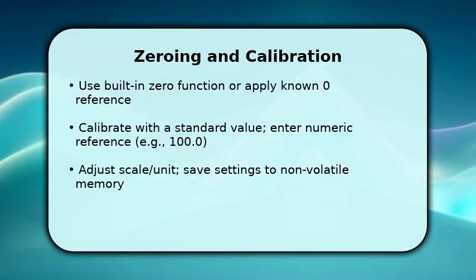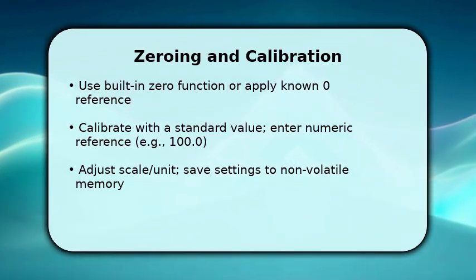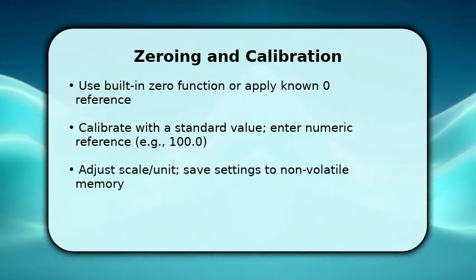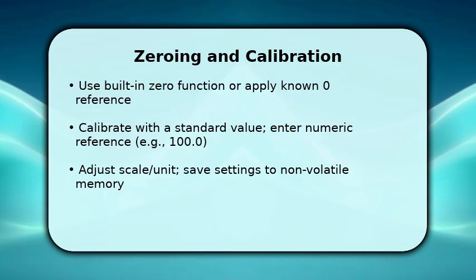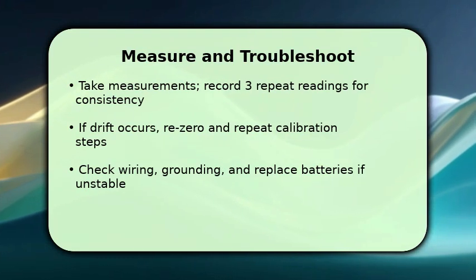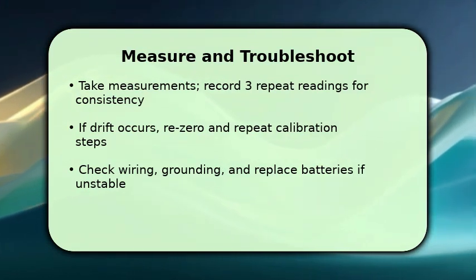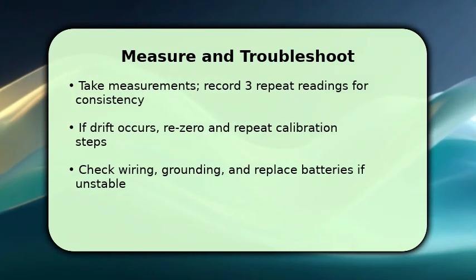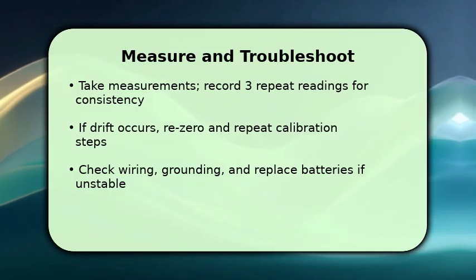Make sure to set the desired scale and units, then save settings to non-volatile memory so your calibration persists after power cycles. You finish by taking measurements and ensuring consistency in results. Perform 3 repeat readings and average them when needed. This reduces random noise and gives you confidence.